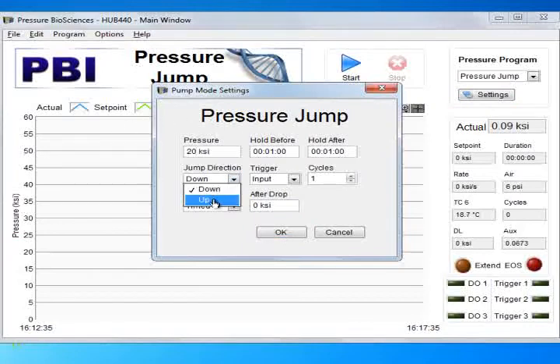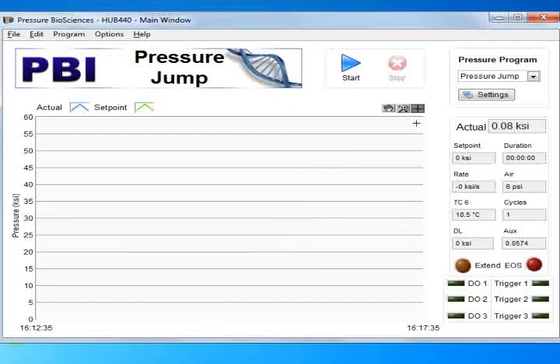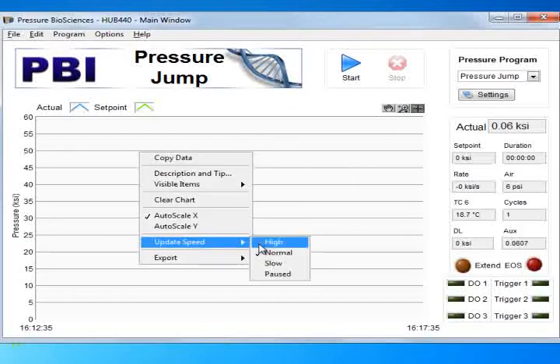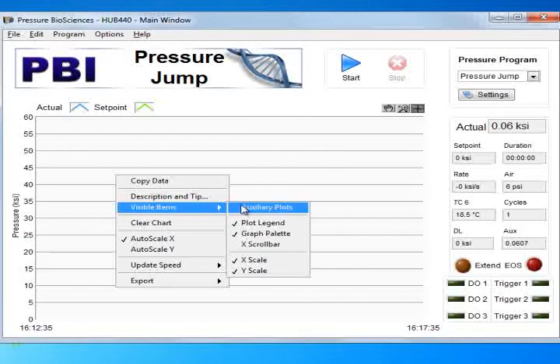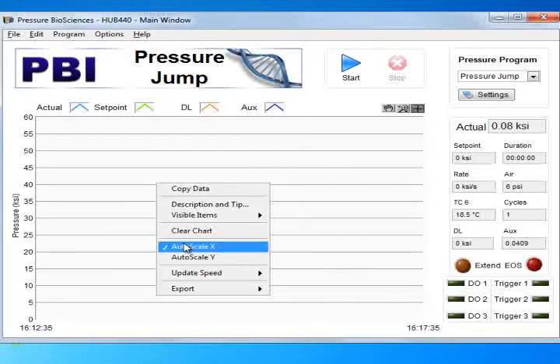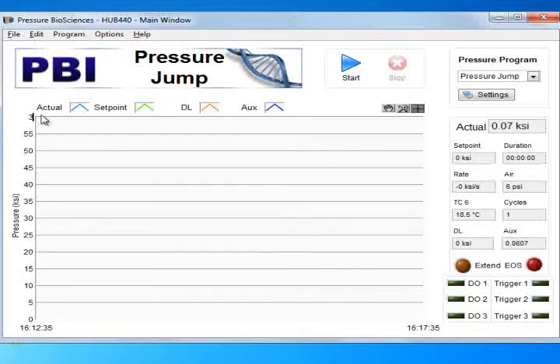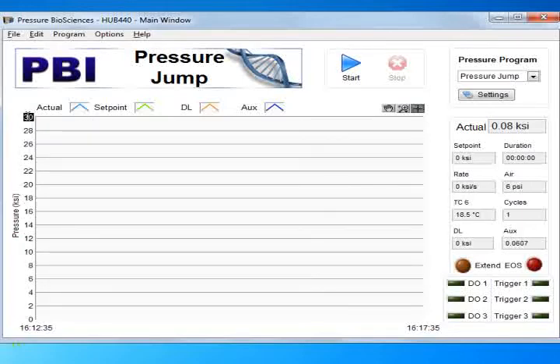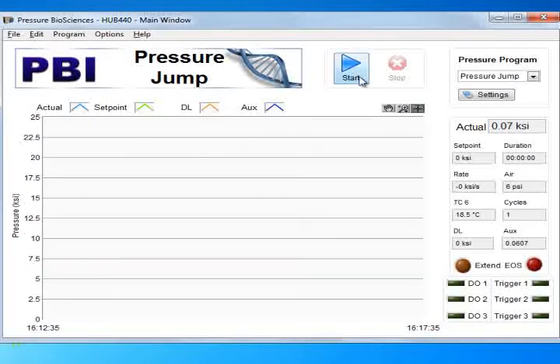Let's watch this process. We enter 20,000 psi as target pressure, 30-second hold time, 10 seconds hold time after the pressure jump. The jump direction is up, none for trigger, timed end of run. When we press OK and choose to display the auxiliary pressure transducer signal at the high speed data acquisition option, auto scale the Y axis, press start.